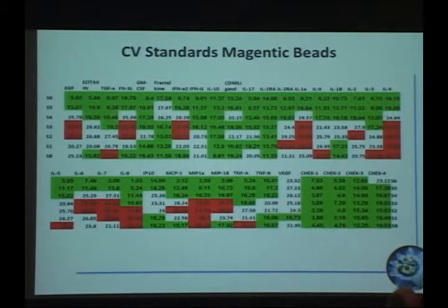I can say briefly now just what they are. CHEX-1 checks the performance of the instrument. CHEX-2 checks the addition of streptavidin phycoerythrin, which is the last step of the ELISA assay. And CHEX-3 checks the addition of the detector antibody. So anything not within a 30% range would be not acceptable, meaning the well could be disqualified as to not receiving enough detector antibody, not receiving enough SAPE, etc.